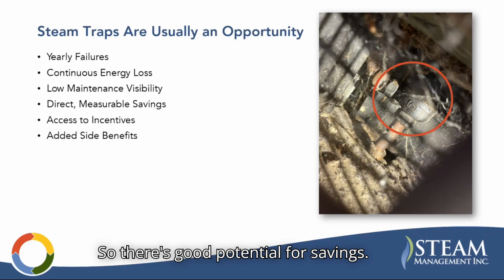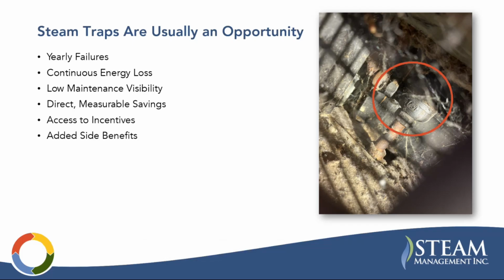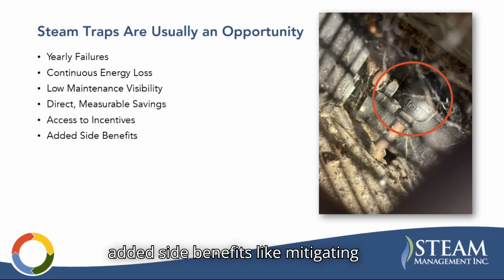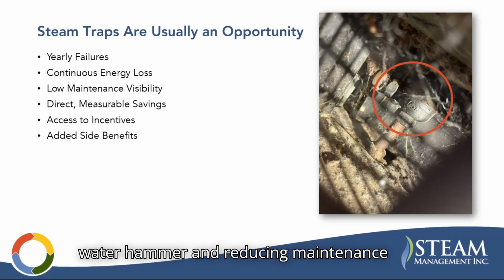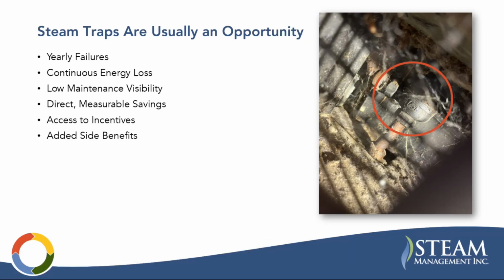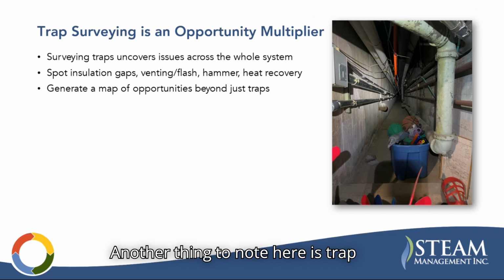So there's good potential for savings. It's direct measurable savings. It's fairly easy to calculate the energy loss from the failed traps. There's usually access to incentives for repairing those traps, and then there are added side benefits like mitigating water hammer and reducing maintenance requirements. The other thing to note here is trap surveying is an opportunity multiplier. So this is a great first step for us into the development. When you survey steam traps, you are seeing the whole system, basically every foot of piping in the system. We're walking it down and seeing it.